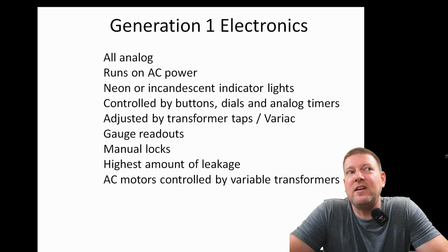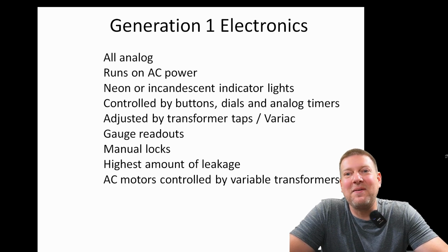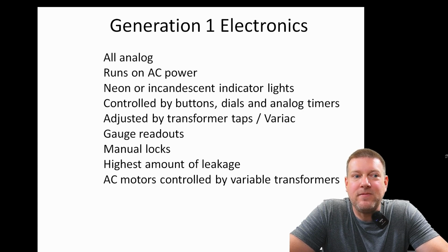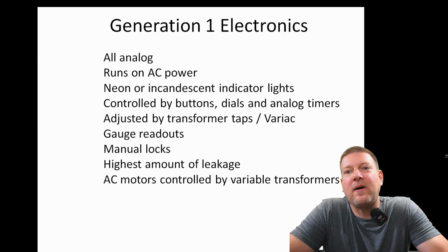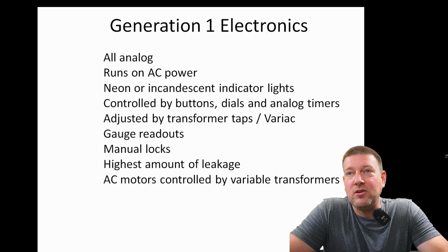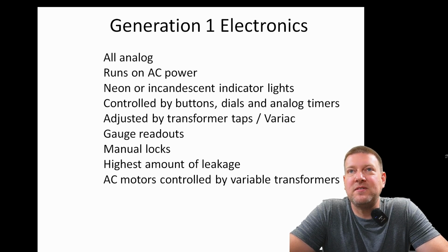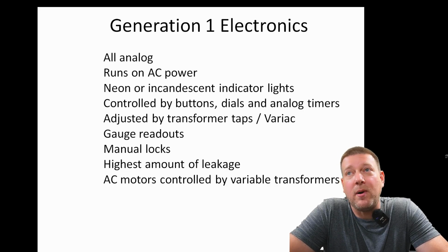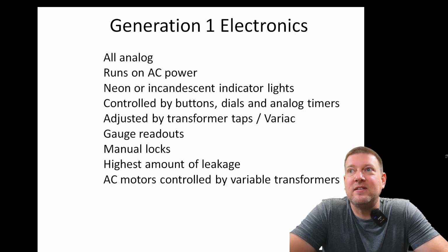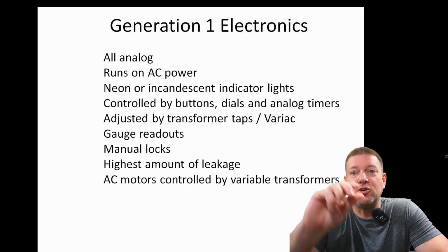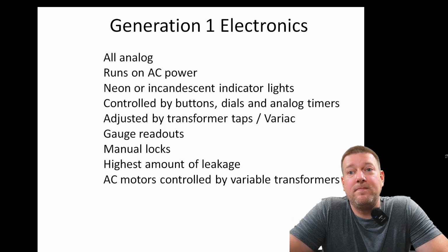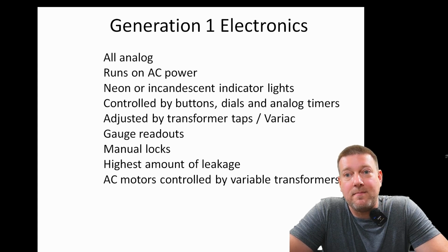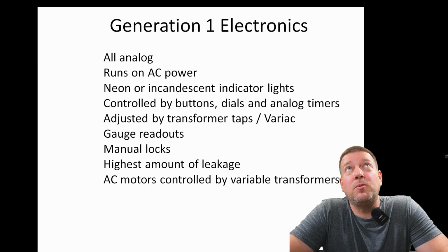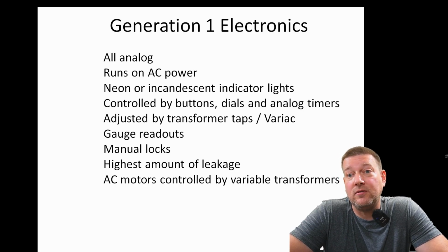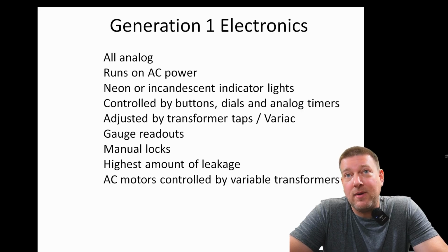They have neon or incandescent indicator lights. This is a dead giveaway. When I see neon lights instead of LEDs, it means, oh man, is this whole thing powered by AC power? And that usually means yes, and it usually means it is a Gen 1 electronic, okay? Doesn't necessarily mean it's old, again. They're normally controlled by buttons, dials, and analog timers, it's true, like watch timers. And it's crazy because I still see, to this day, things like infant warmers controlled by a rotary timer. So what happens if that timer jams up, which, by the way, I did see? That means the baby is supposed to be on a 15-minute timer, and it's just sitting there getting cooked, all right? Analog is sometimes not better, right?